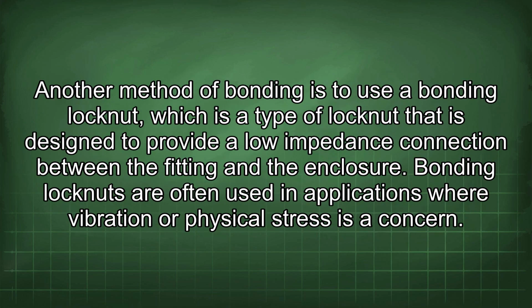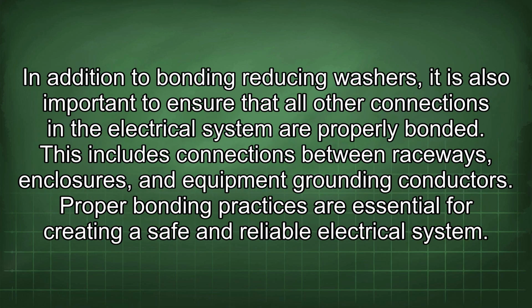Another method of bonding is to use a bonding lock nut, which is a type of lock nut that is designed to provide a low impedance connection between the fitting and the enclosure. Bonding lock nuts are often used in applications where vibration or physical stress is a concern. In addition to bonding reducing washers, it is also important to ensure that all other connections in the electrical system are properly bonded. This includes connections between raceways, enclosures, and equipment grounding conductors. Proper bonding practices are essential for creating a safe and reliable electrical system.